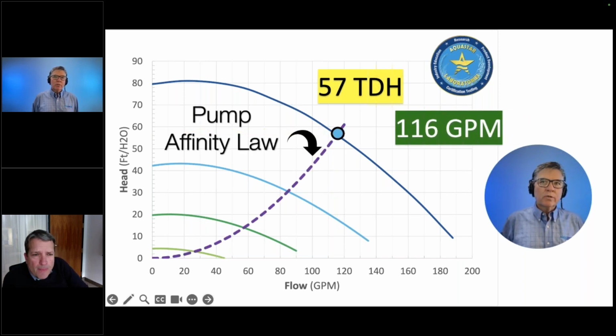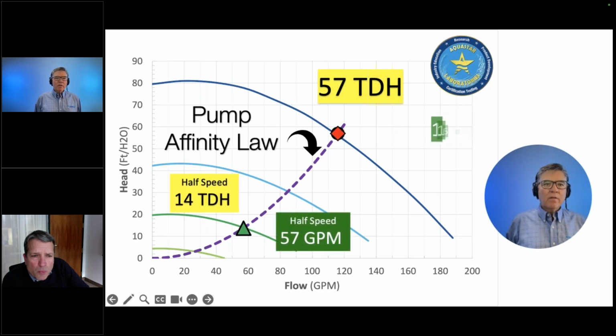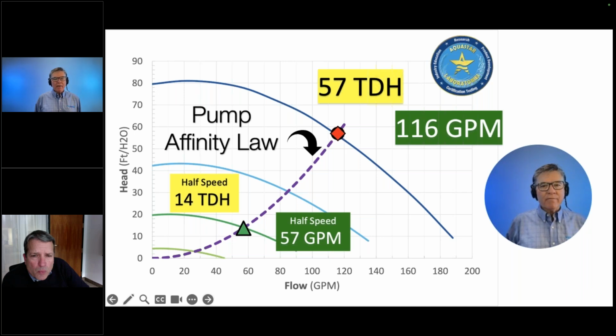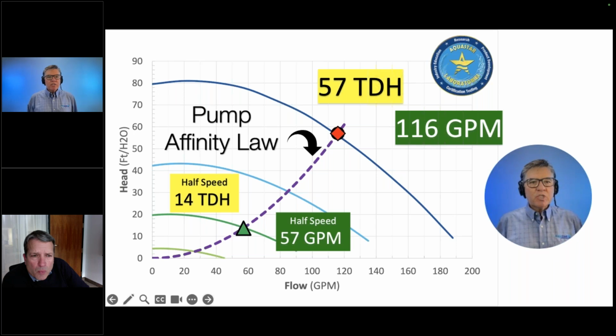Now, another tool in your toolbox is going to be the pump affinity law. This is a law of physics that you can absolutely trust. Again, I'm not going to try and teach this, but there are formulas and even TDH calculators from some manufacturers where you can use this. The one that's going to matter is, if we reduce the RPM by half, the flow is going to reduce by half. So on the pump affinity law, speed and flow are proportional. It's a 1-to-1 relationship, so you can just do the math and find out your flow rate.